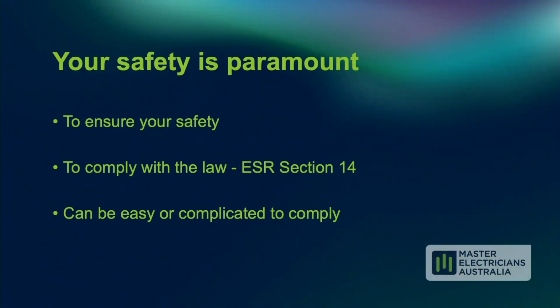To ensure that your electrical work is performed safely, it is essential to work de-energised. It's also a requirement of law under Section 14 of the Electrical Safety Regulation 2013. Arc flash is a serious risk even when only working near energised components, and it's working near that we get most of those issues starting to occur. When people are pulling new circuits into a switchboard, a lot of the time they're not considering those line side terminals before they proceed, so they do need to isolate for those.